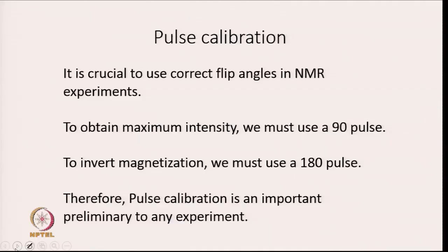It is crucial to use correct flip angles in NMR experiments. NMR is a low sensitive technique, so we want to get maximum signal from each scan. To obtain maximum intensity, we must use a 90-degree pulse, and to invert magnetization we must use a 180-degree pulse. The correct length of the pulse should be maintained, and therefore pulse calibration is an important preliminary to any experiment.